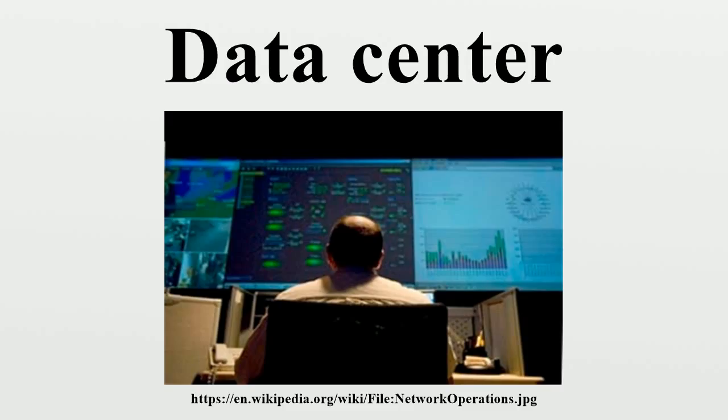Tier 1 status would allow 1,729.224 minutes or 28.817 hours. Tier 2 status would allow 1,361.304 minutes or 22.688 hours. Tier 3 status would allow 94.608 minutes or 1.5768 hours. Tier 4 status would allow 26.28 minutes or 0.438 hours. The Uptime Institute also classifies the tiers in different categories.